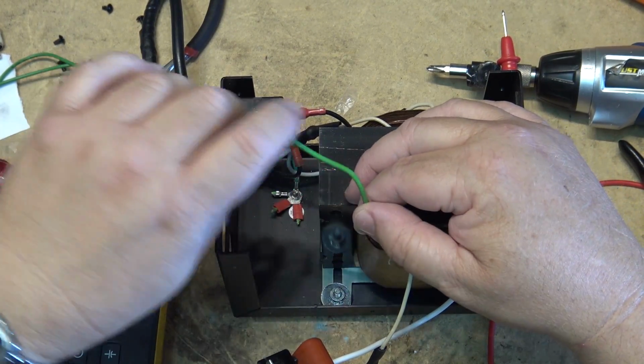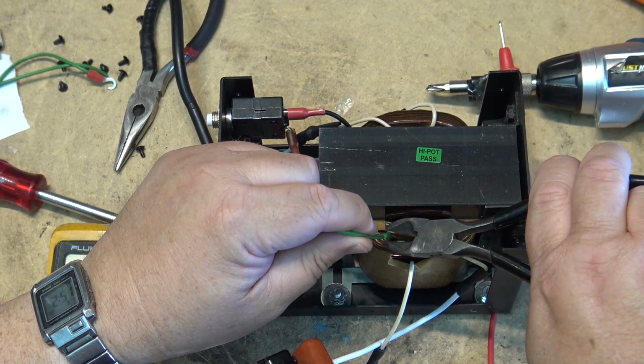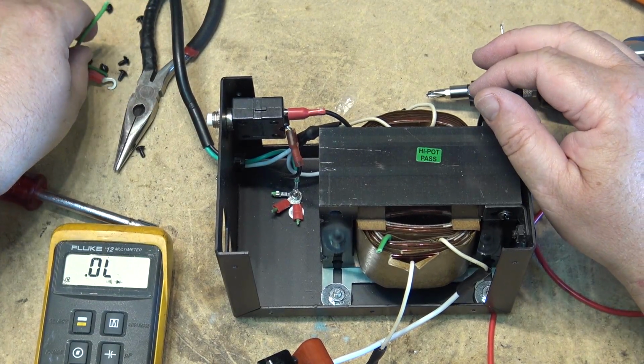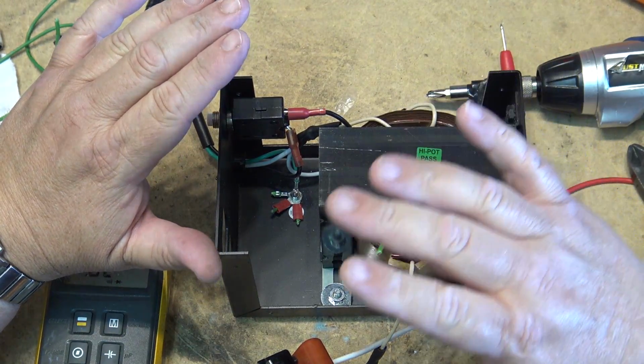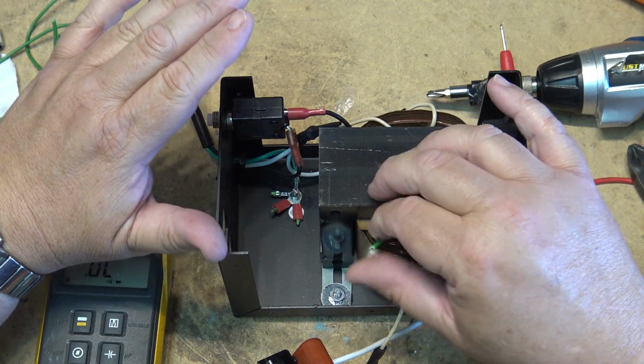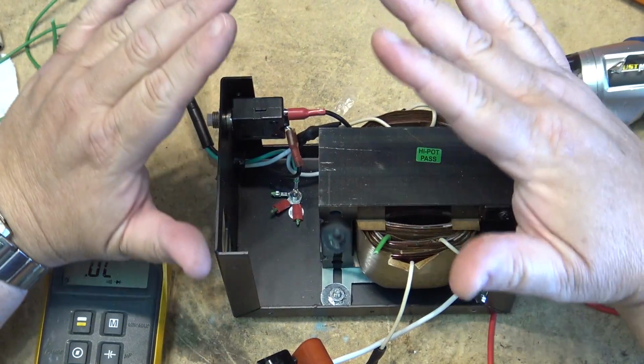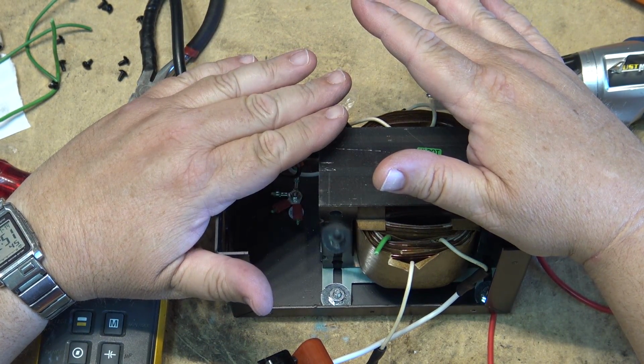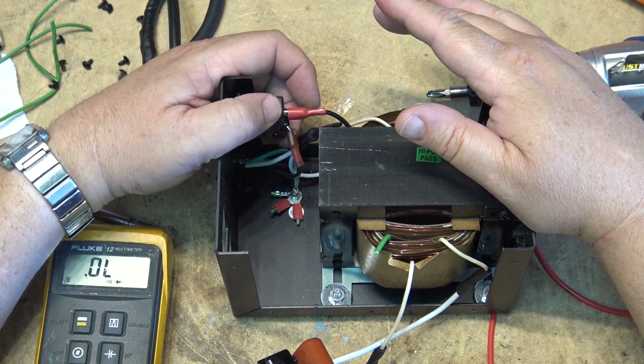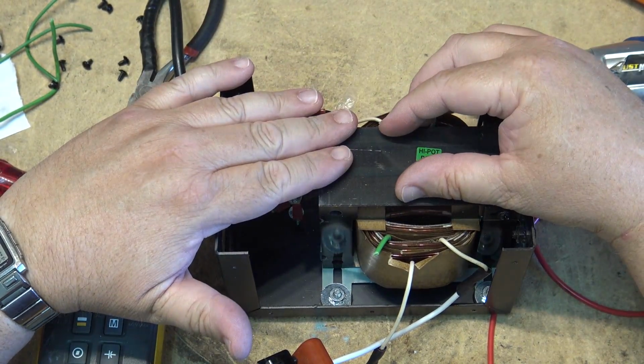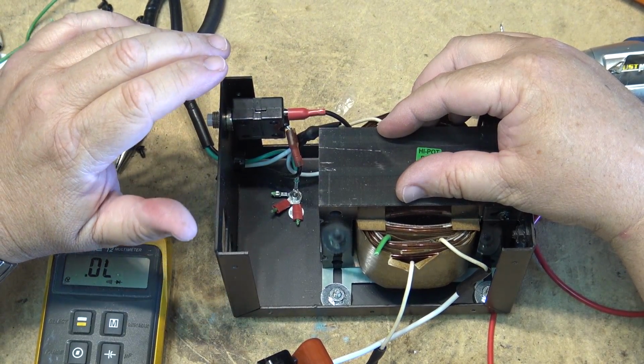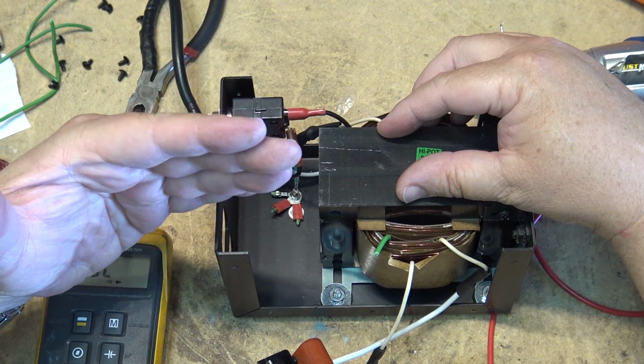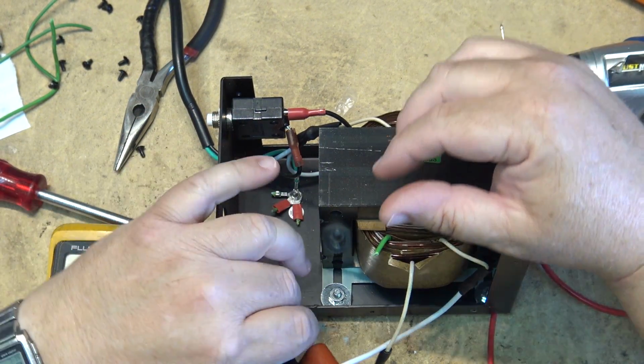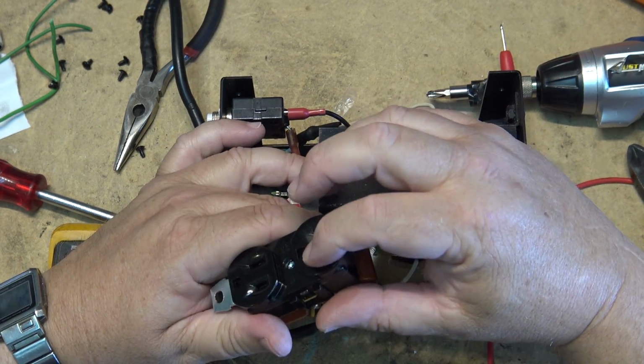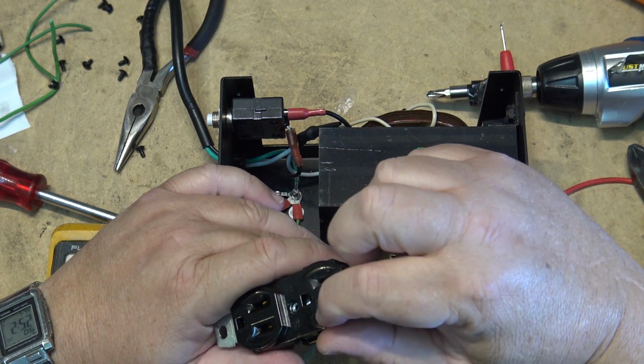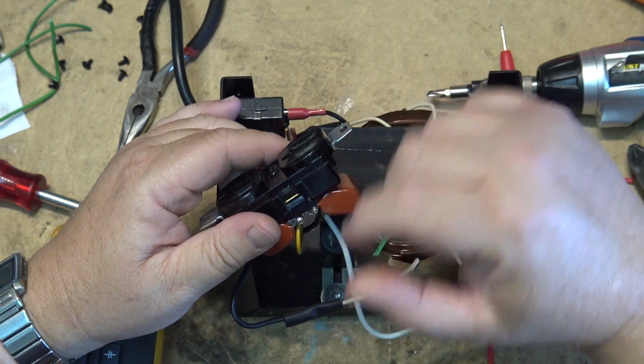And the reason you want both sides completely isolated, I'm just going to cut this one here off too, as it's not needed, and we'll just put some heat shrink on there. The reason you want your plug totally isolated from ground fault is how an isolation transformer protects the service person who's servicing. These are used by service people to service electronic equipment.